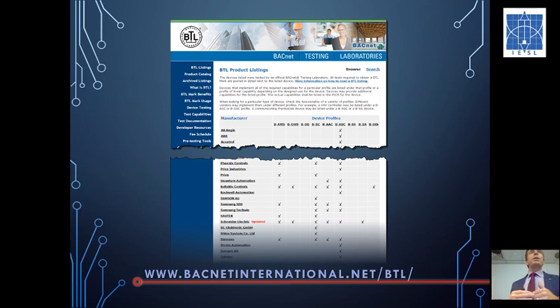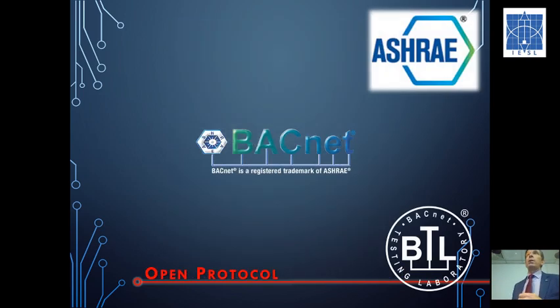Once BACnet tests and it's been accepted, BACnet will then publish on their website, which is a public website, the profile, the PICS and the BIBBs of the device. Which means if anybody comes along and says, I have a BACnet device, you as an engineer or as a person interested can actually go to this public website and search that controller and see if it delivers what they say, see if it's been tested by BACnet, because the BACnet testing laboratories are the policemen that ensure that when people provide these devices, they actually live up to what they claim. Because we're trying to exchange information. They're the rules about exchanging information.